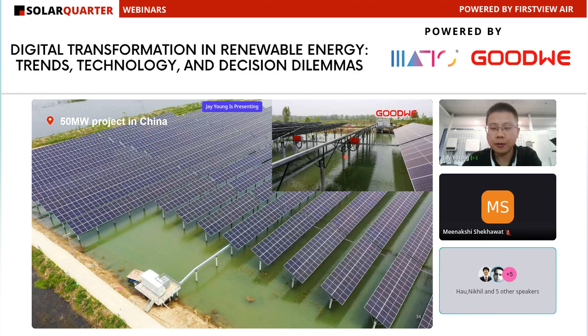This is the station in China. You can see that all the modules or the inverters are installed above the lake. In this kind of environment, it's very high humidity, and the temperature is also very high, so it is not very friendly for the PV modules. It is easy to get the PID effect, and our inverter itself is just 2.5 meters above the lake, so the humidity is very high. But for our inverter, we have IP66 and C5 corrosion level to ensure the inverter's own stability, and for the modules we also can provide PID solutions to prevent the PID effects.